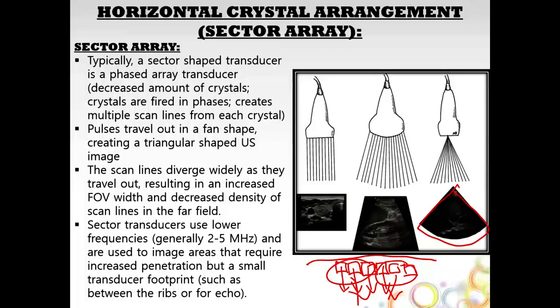sector array. Just like a convex array, which is this one here, in the far field you get this divergence of the beams. So you do get a decreased resolution in the far field. Sector transducers are very low frequency transducers, 1 megahertz to 5 megahertz. So you use these in places of the body that require a lot of penetration. And the advantage of them is, since they don't have such a long row of crystals, they have a smaller footprint, so a smaller area that touches the body. So they're really good for getting in between ribs and areas where you need a smaller transducer footprint.